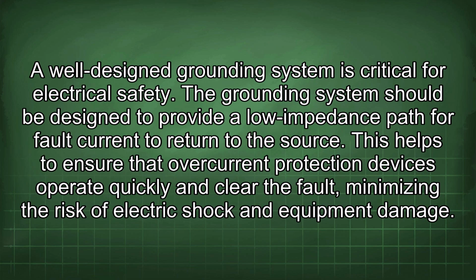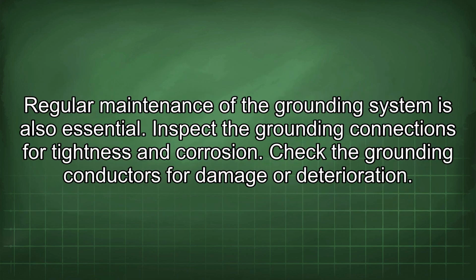A well-designed grounding system is critical for electrical safety. The grounding system should be designed to provide a low impedance path for fault current to return to the source. This helps to ensure that overcurrent protection devices operate quickly and clear the fault, minimizing the risk of electric shock and equipment damage. Regular maintenance of the grounding system is also essential.